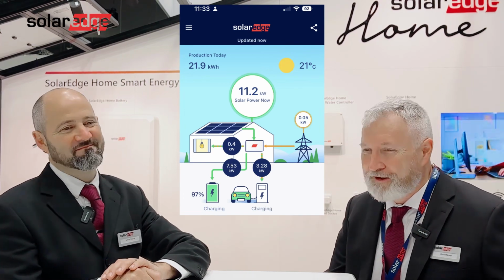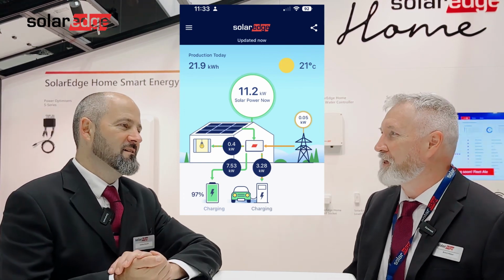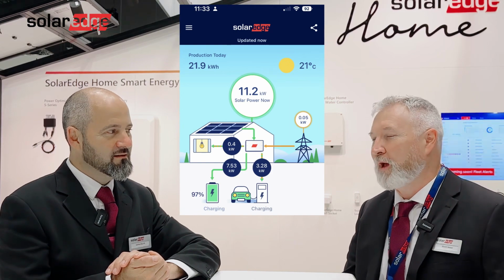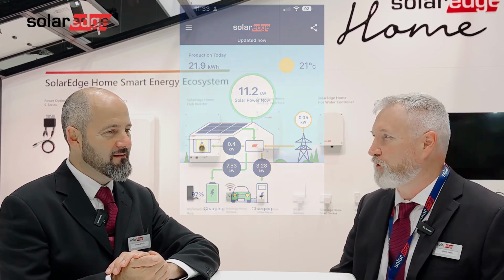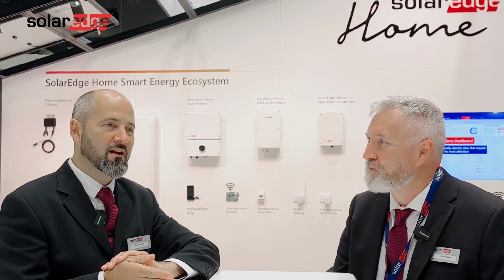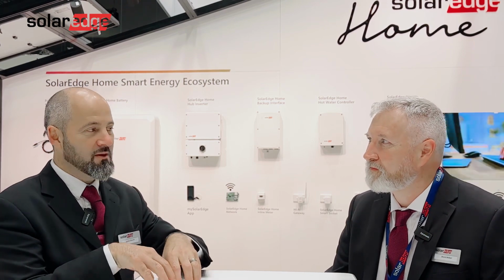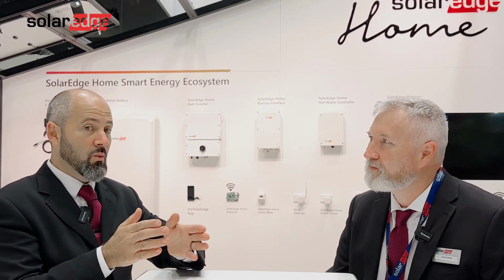So James, a bit of a technical explanation of what are we seeing here when we're getting these phenomenal outputs of our roof off a smaller inverter? Sure, and I've seen the same on mine. I've got a 10 kilowatt single phase inverter as well, and sometimes I'm seeing 14, 15 kilowatts phenomenal production. But the interesting thing is, it isn't the inverter that's doing this. It's the production that you're seeing. You're not seeing the AC output from the inverter. And that's where people often get tripped up. They look at it and say, what is the inverter's production? It's not, it's the PV production.